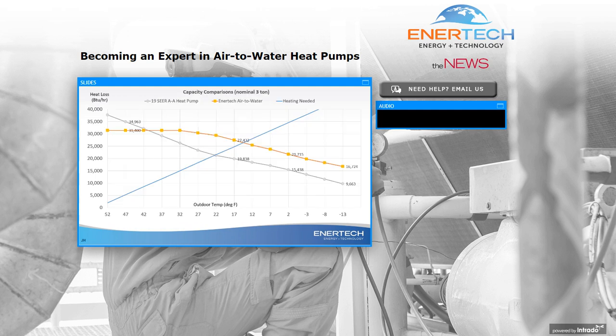When we look at capacities, same thing, because this is a heating designed unit. The blue line you see going at an angle there is the heat load of the space. In orange is the air-to-water heat pump versus a 19-SEER heat pump in gray. And where the blue line crosses the line, either air source or the air-to-water heat pump, is the balance point. The farther out we can go on the balance point, the less backup heat we need. So having higher capacity at those colder temperatures is a pretty big deal. In fact, you can see here we gain somewhere in the neighborhood of between 5 and 7 degrees versus even the highest efficiency air source heat pumps, where we can hold on until colder temperatures before we need any backup heat.